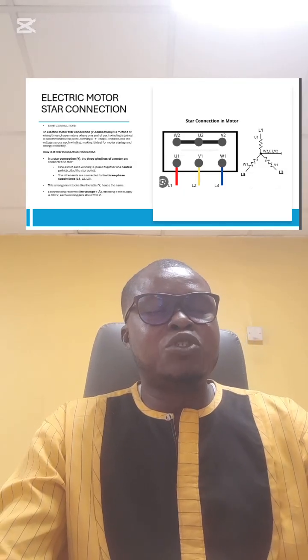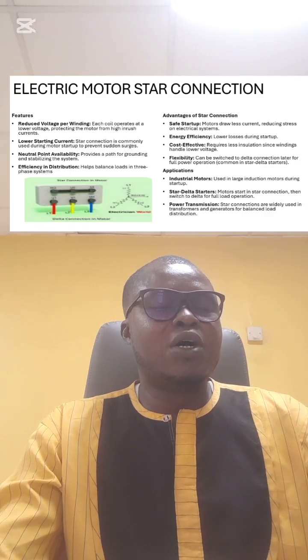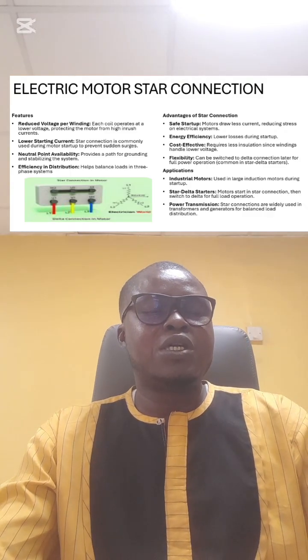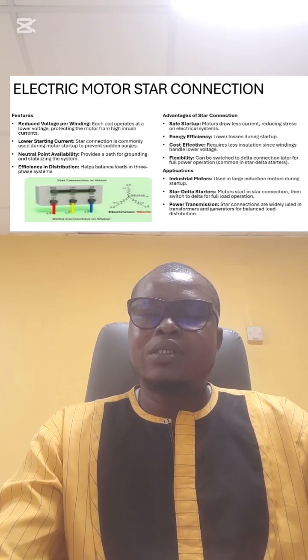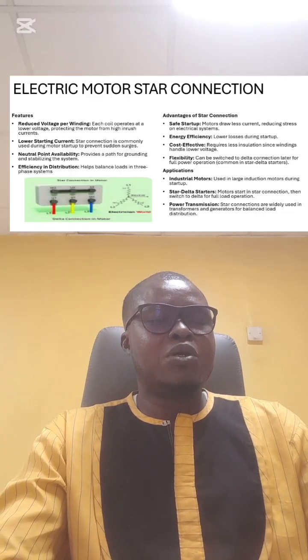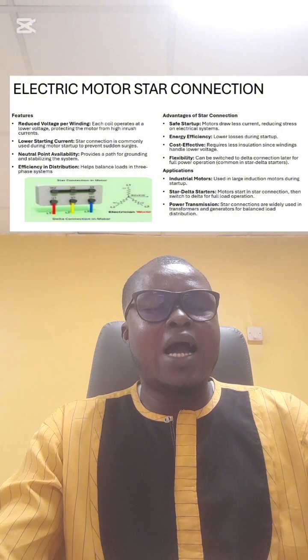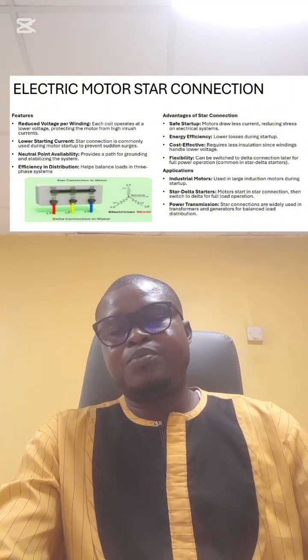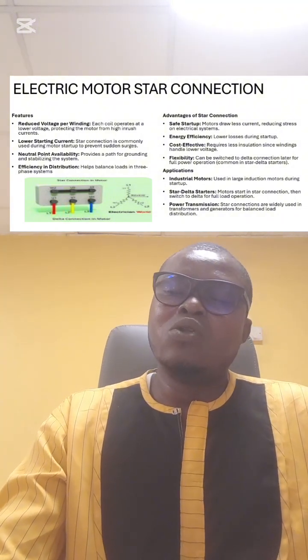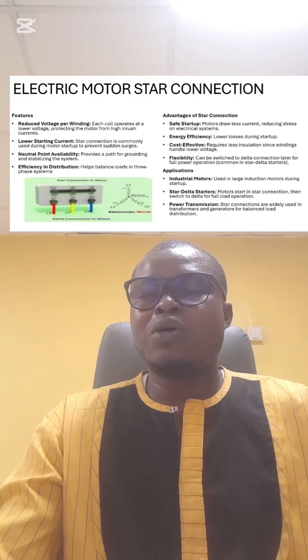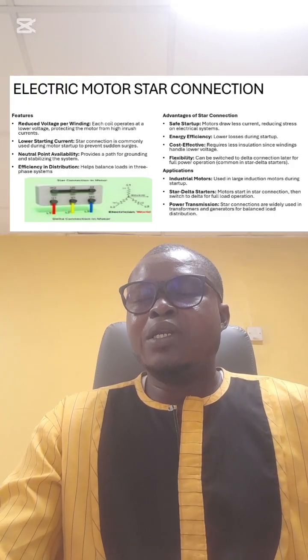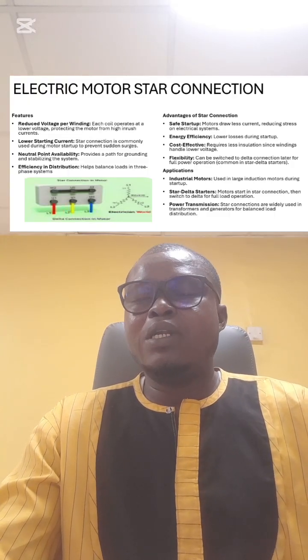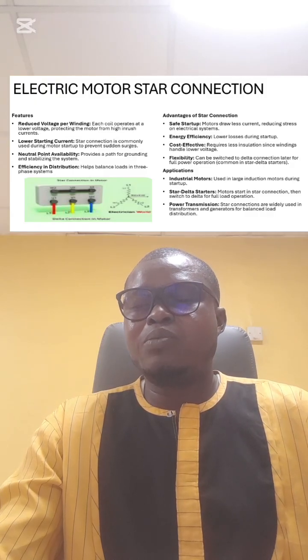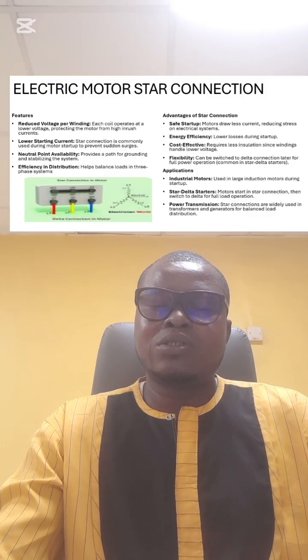Now, there are features of this particular connection. One of the features is to reduce the voltage per winding, meaning that each coil operates at a lower voltage, protecting the motor from high inrush current. Another is the lower starting current, meaning that the star connection is commonly used during motor startup to prevent a sudden surge.